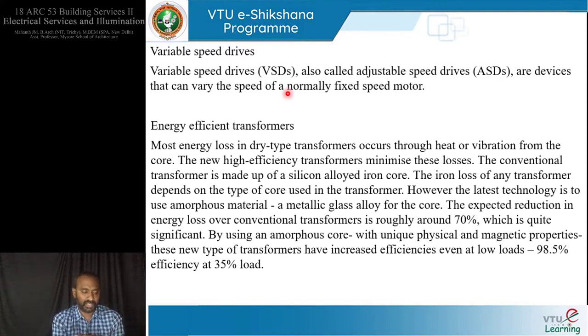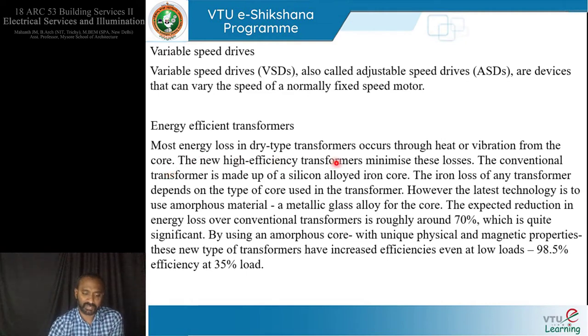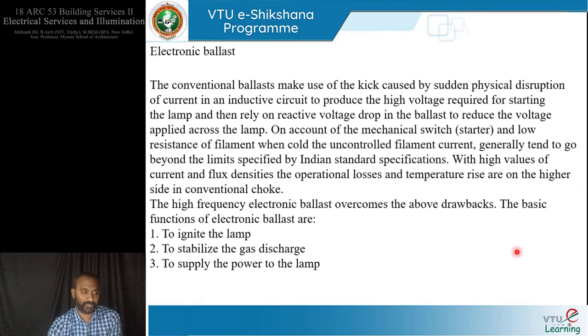Energy efficient transformers address losses that occur mainly through heat and vibration from the core in conventional dry-type transformers. New high-efficiency transformers minimize these losses by replacing the silicon-alloyed iron core with an amorphous material — a metallic glass alloy. This results in increased efficiencies even at low loads, with efficiencies as high as 98.5% even at just 35% load.